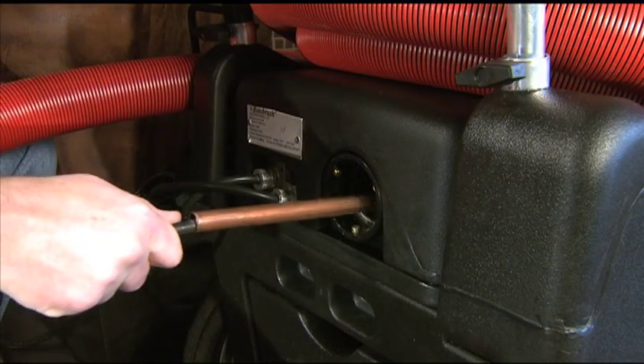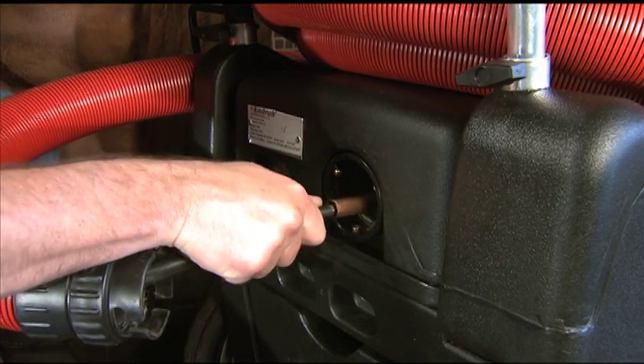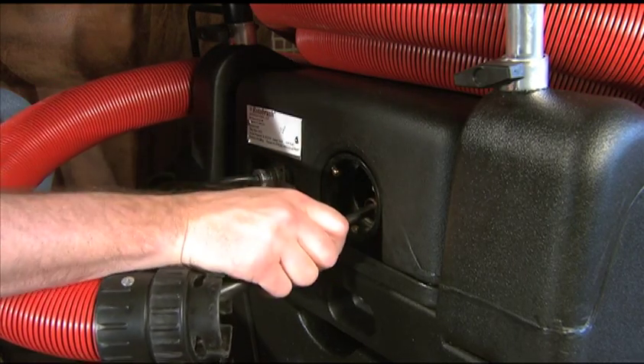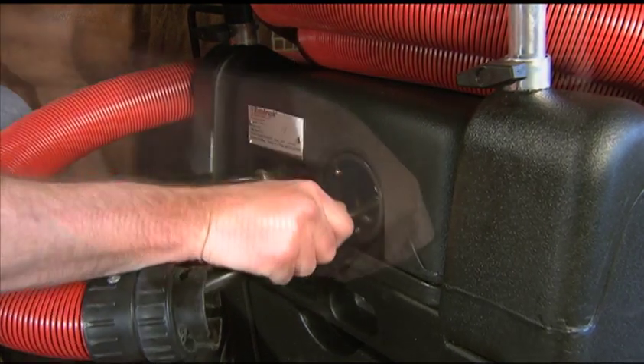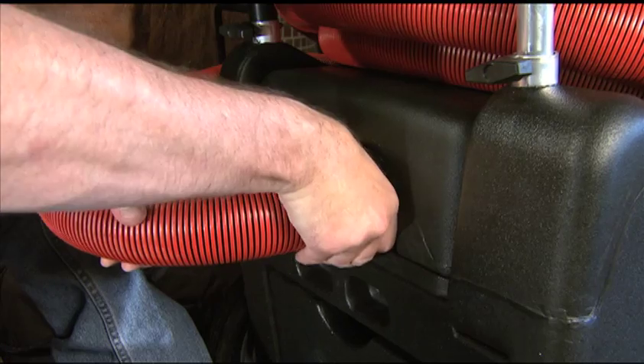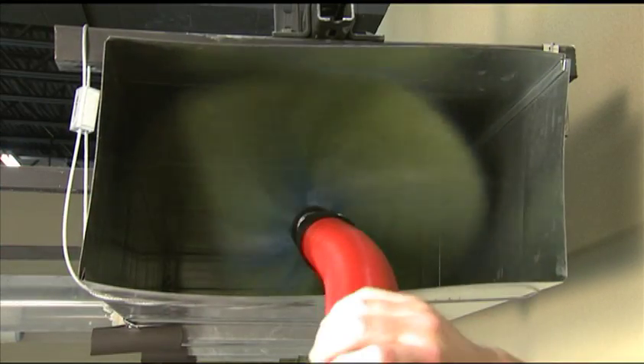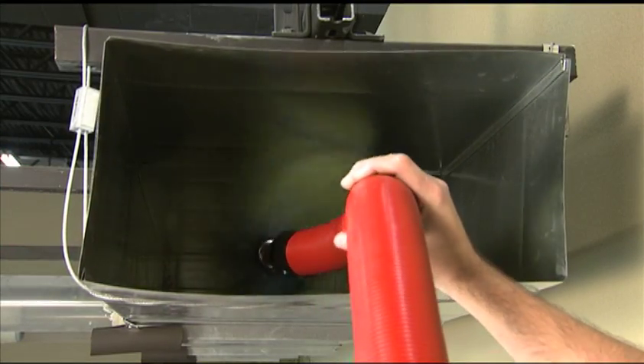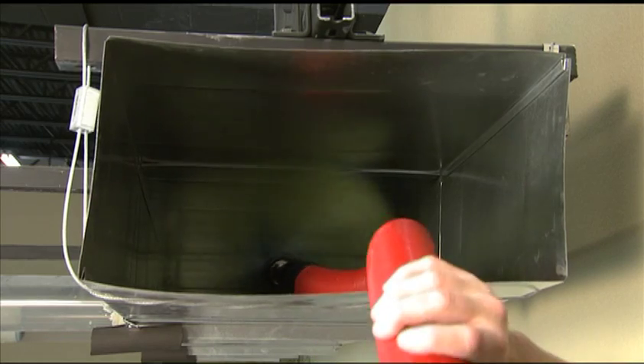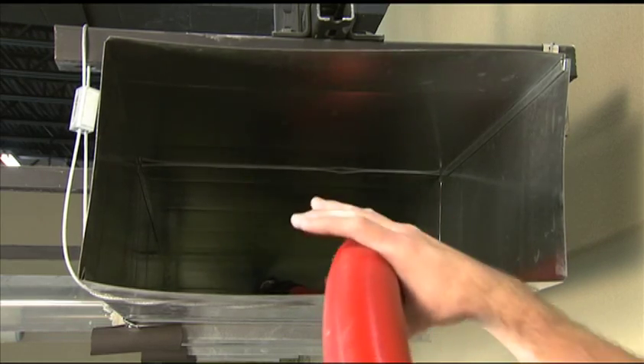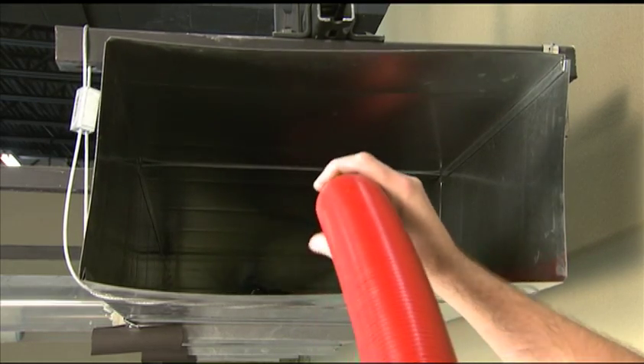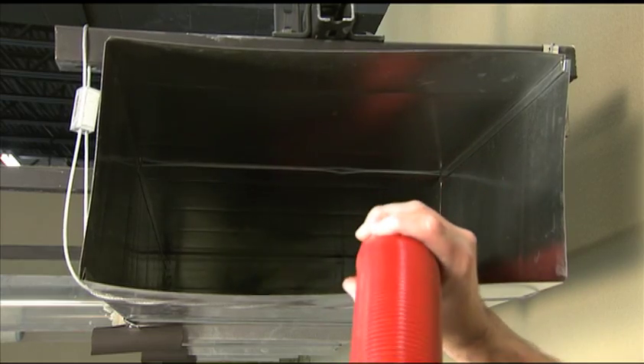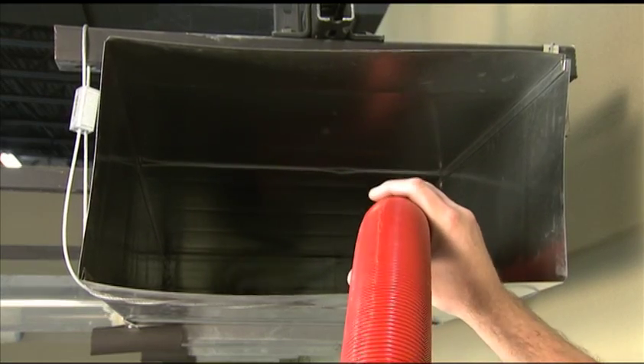The Rotobrush has been designed for low maintenance. A couple of items you want to look at are the torque adjustment of the machine and the filtration. We're going to talk about the torque adjustment first. Torque is the driving power of the brush. Basically, you turn it on, the brush spins. As you're going through ductwork and your brush tends to hesitate or stop, your torque may be adjusted improperly. It's preset before it leaves the factory, but during shipping, items can shift, and so it may need to be adjusted, but it's a really easy process.